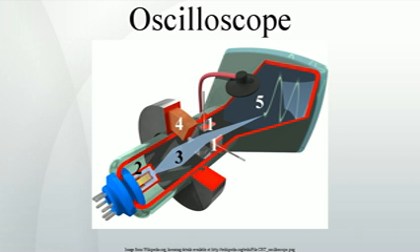A vertical input goes to a frequency-compensated step attenuator to reduce large signals to prevent overload. The attenuator feeds a low-level stage, or a few, which in turn feed gain stages, and a delay line driver if there is a delay. Following are more gain stages, up to the final output stage which develops a large signal swing, tens of volts, sometimes over 100 volts, for CRT electrostatic deflection.